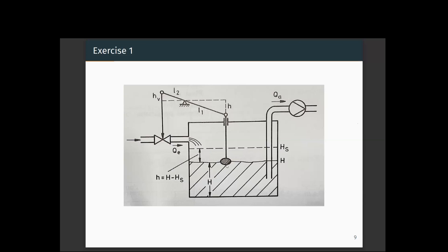Currently the float senses that the water level is at a lower position, so this valve is being opened more so that more water comes in and the water level rises to the set point. This can only happen if QA is fixed — the water pumped out is at a fixed rate — only then can we control the level of the water.